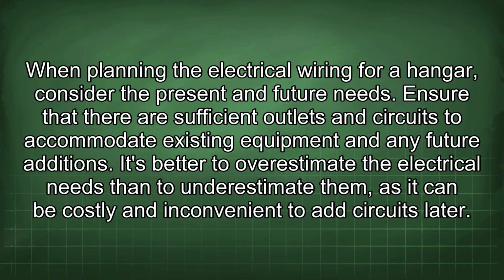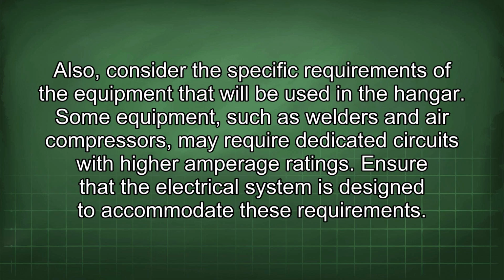When planning the electrical wiring for a hangar, consider the present and future needs. Ensure that there are sufficient outlets and circuits to accommodate existing equipment and any future additions. It's better to overestimate the electrical needs than to underestimate them, as it can be costly and inconvenient to add circuits later. Also, consider the specific requirements of the equipment that will be used in the hangar. Some equipment, such as welders and air compressors, may require dedicated circuits with higher amperage ratings. Ensure that the electrical system is designed to accommodate these requirements.